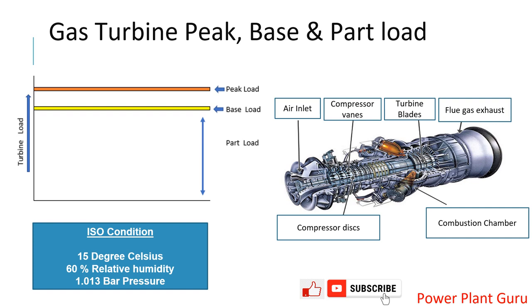Peak load conditions are not healthy for the machine. Only in extreme requirements or emergencies do power plant operators go for peak load. As soon as the emergency or higher load requirement reduces, they try to resume base load operations for best life and best efficiency. If there is a further reduction in load required, the operator reduces load from base load, and any load lower than base load where the IGV starts closing from its full open position is called part load. From full speed no load up to base load, for whatever reason, this is part load condition.